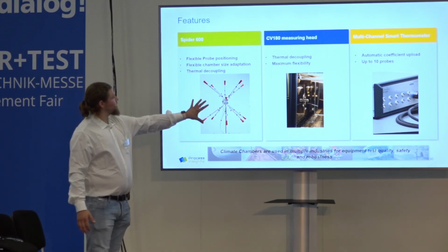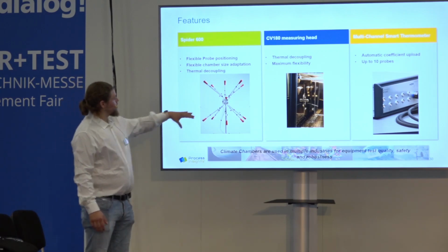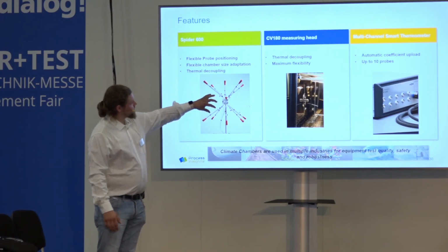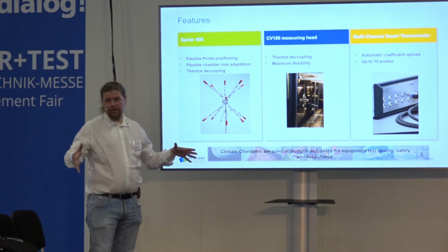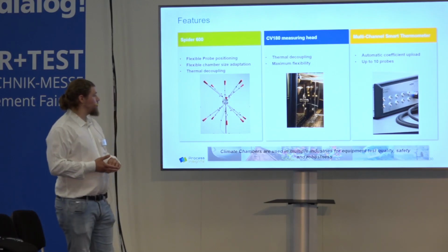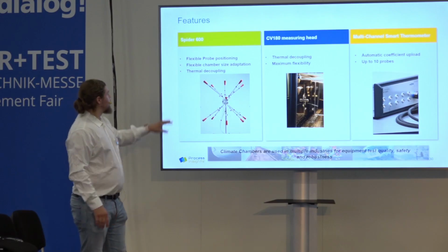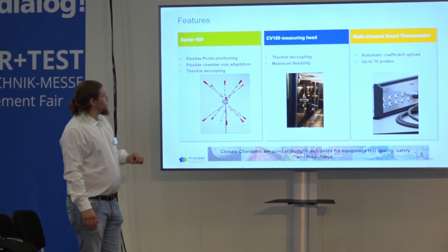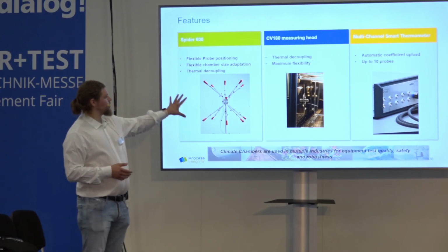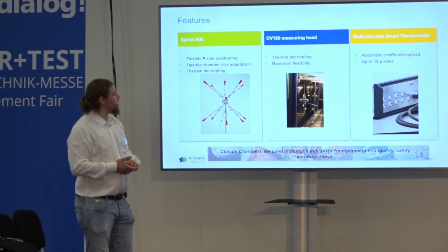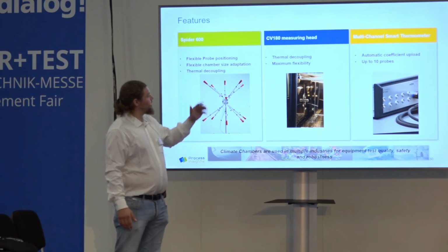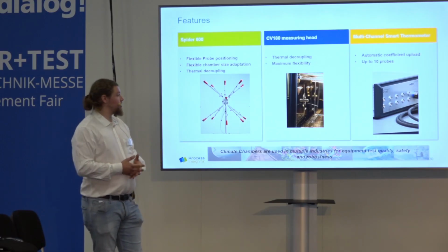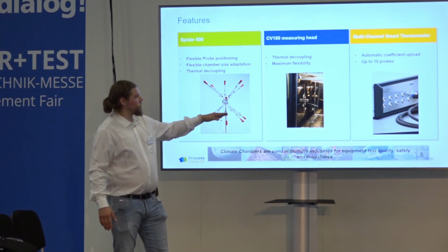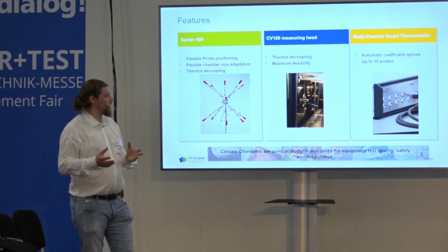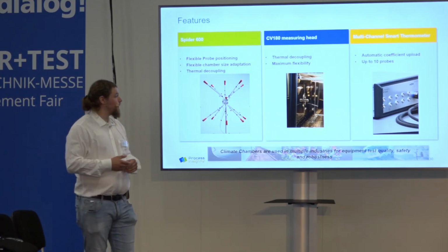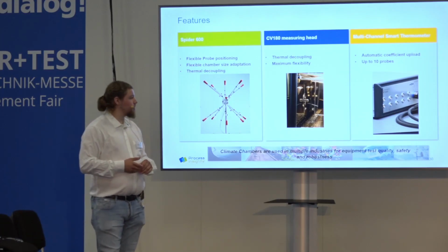With the spider, a solution to take care of the temperature probe locations, you can extend and lower the distance between 30 and 60 centimeters square, so that you can apply it to different climate chamber measures and different useful volume requests. You have a thermal decoupling of the probes, and this is a representative value for the temperature in the chamber, which then applies to all the tests which are made. The big change is that the CV180 measuring head is no longer in the chamber, but applied from the outside. We re-engineered our measuring head so that there will be no thermal loads anymore influencing the conditions of the chamber.